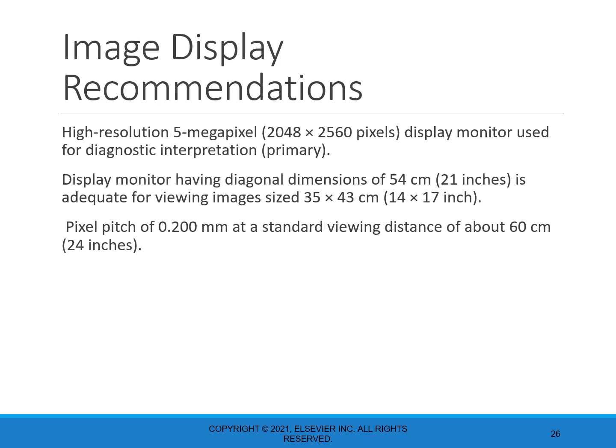They must also have a diagonal dimension of 54 centimeters or 21 inches, which is adequate for assessing a 14 by 17 inch X-ray. A pixel pitch of 0.2 millimeters at a standard viewing distance of about 60 centimeters or 2 feet is required.